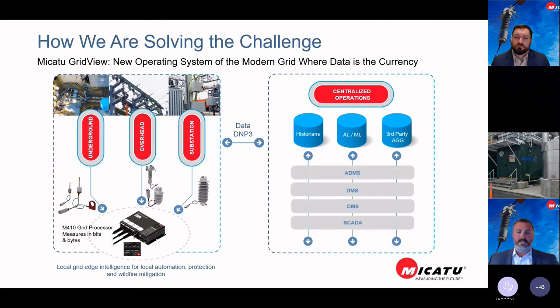The GridView M410 processor, shown here at the bottom of the screen, converts all the sensor data being collected and transfers it back through numerous communication protocols. DNP3 is very accurate and is usually the preferred method, sending data back in a standard format into the centralized operational system many of our customers have. Providing that data seamlessly into OT software like an ADMS or DERMS drives a lot of value, helping customers make better choices with less manpower, saving time and money — a big return on investment.